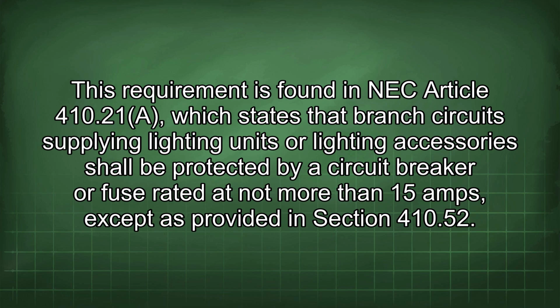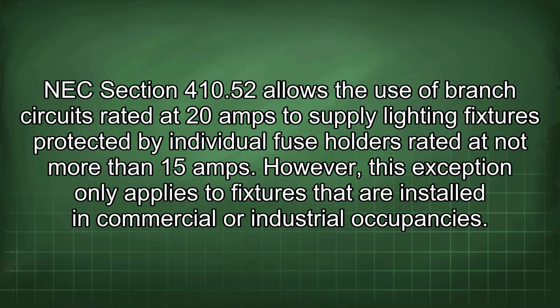410.21a, which states that branch circuits supplying lighting units or lighting accessories shall be protected by a circuit breaker or fuse rated at not more than 15 amps, except as provided in Section 410.52. NEC Section 410.52 allows the use of branch circuits rated at 20 amps to supply lighting fixtures protected by individual fuse holders rated at not more than 15 amps.